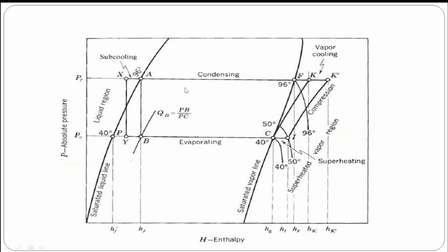So on a pH chart, the superheated vapor region as well as the subcooled region are shown. AX is the subcooling and CI is superheating here. You can see here, both superheating as well as subcooling could be shown in the actual refrigeration cycle. In the ideal case, the refrigerant exits the evaporator as saturated vapor and the liquid refrigerant exits the condenser as saturated liquid at point A, ideally. But theoretically, these are the cases. I hope it is clear.